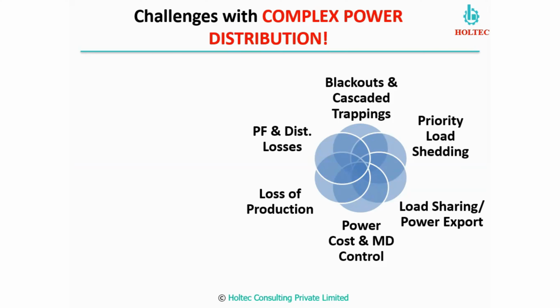Now, the power cost. Power cost is very important. We have to take maximum power from our cheapest sources and minimum power from our costly sources. MD control everybody knows: we cannot exceed the maximum demand from the grid beyond a defined value, otherwise we will be penalized. So this is also a challenge for us. In any case, our MD should not exceed. Then loss of production: when we have nuisance trippings and unprioritized load sheddings, it results in production loss.